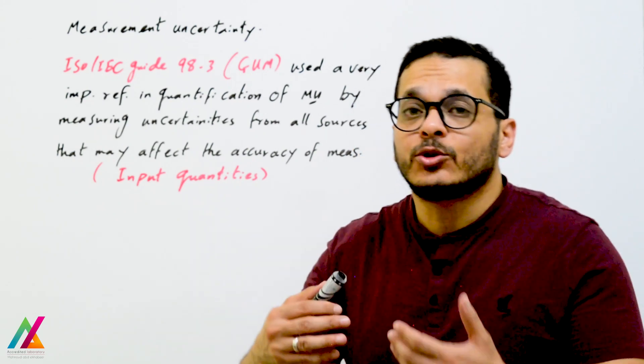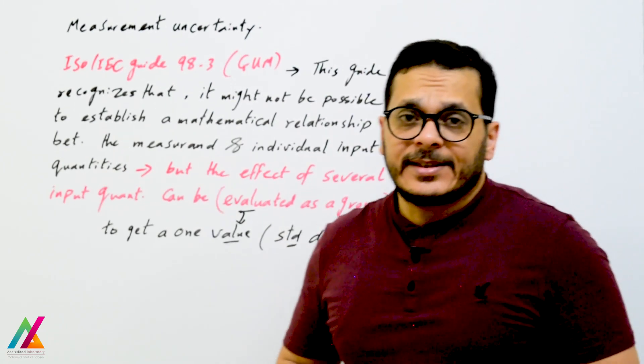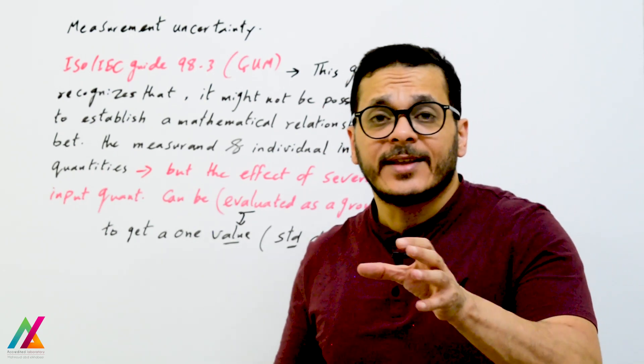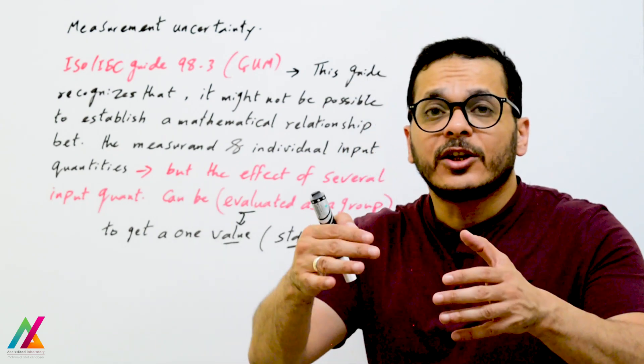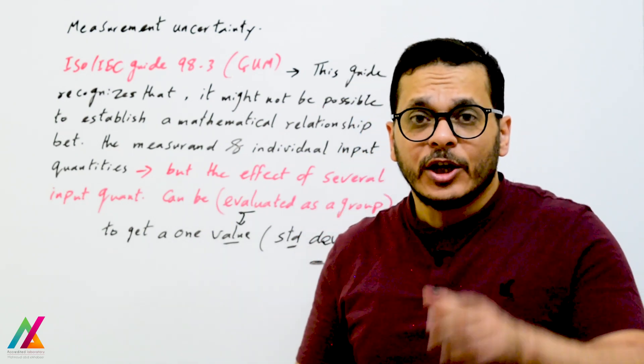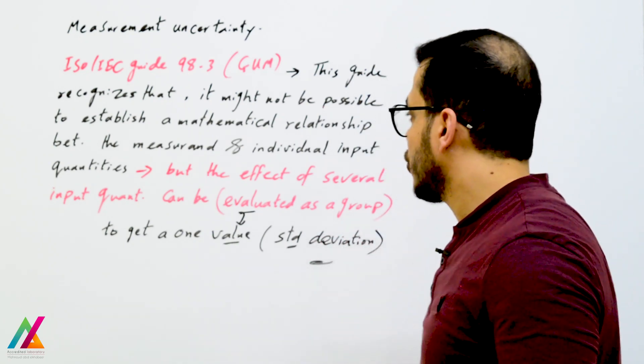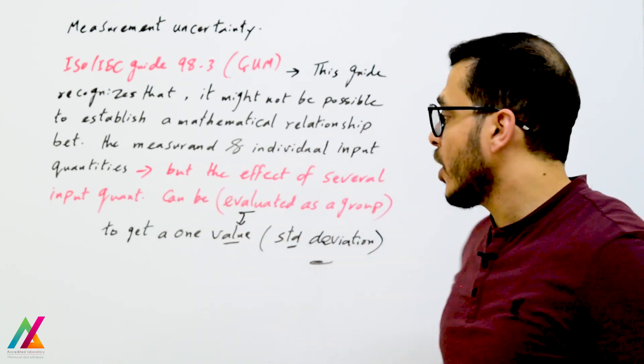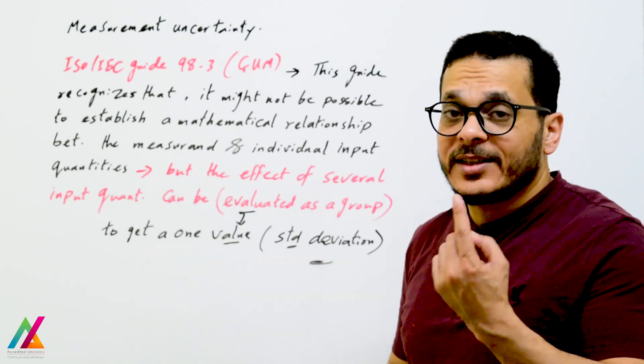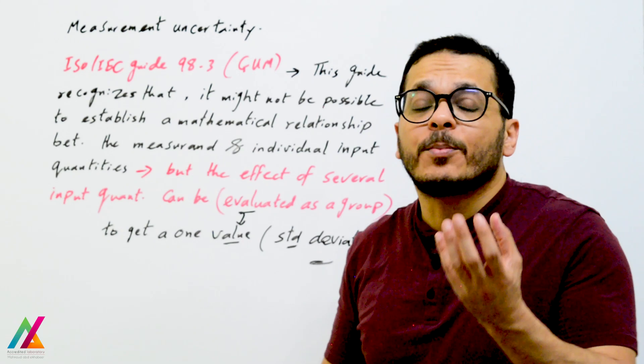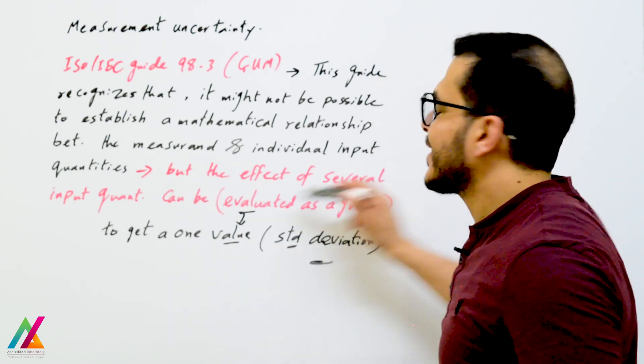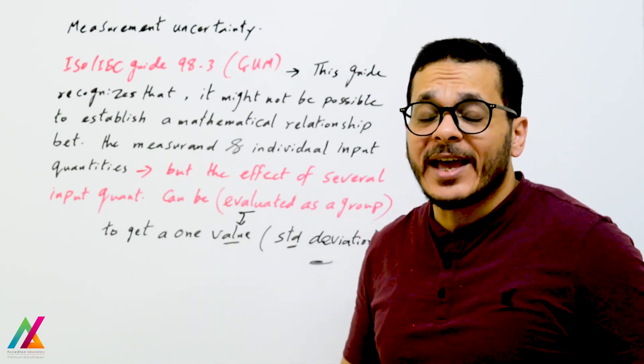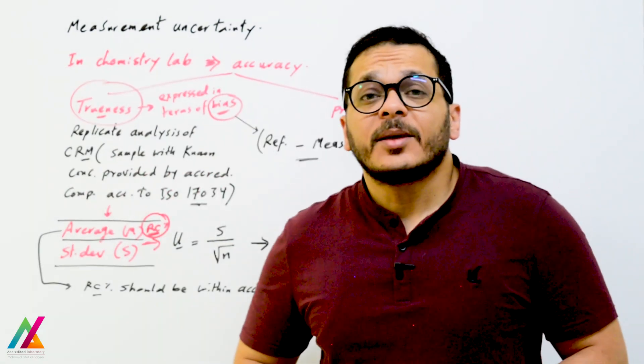This guide recognizes it might not be possible to establish a mathematical relationship between the analyte and every individual input quantity. However, after identifying all input quantities, you calculate the uncertainty from each source, and the effects of several input quantities can be evaluated as a group. These are then combined together to get one overall value — a parameter such as standard deviation from repeatability or reproducibility — which is added to the final result.